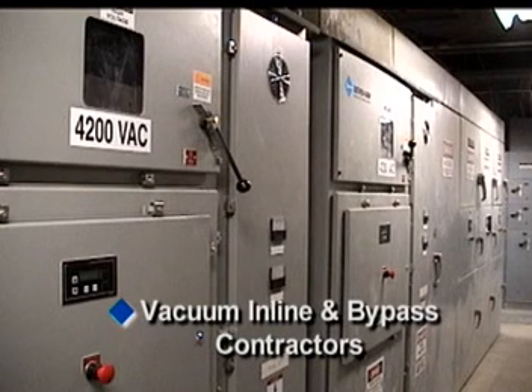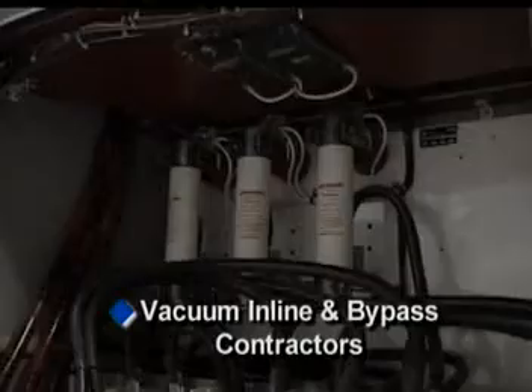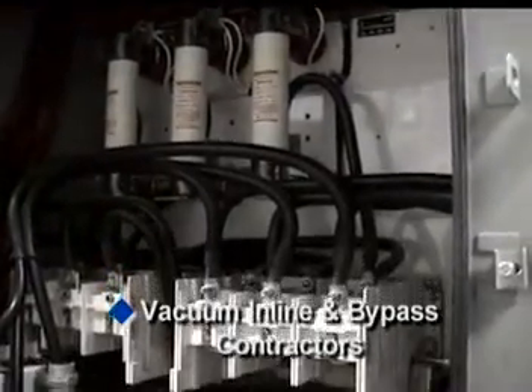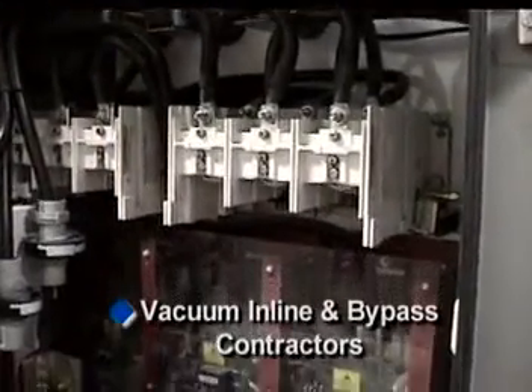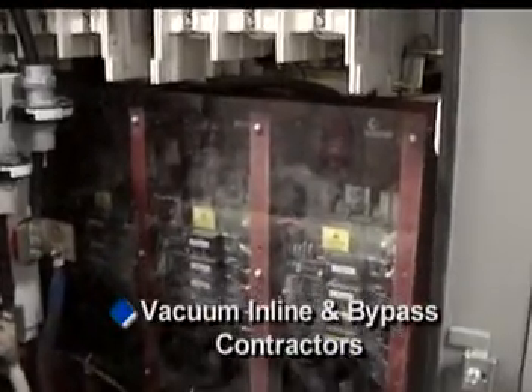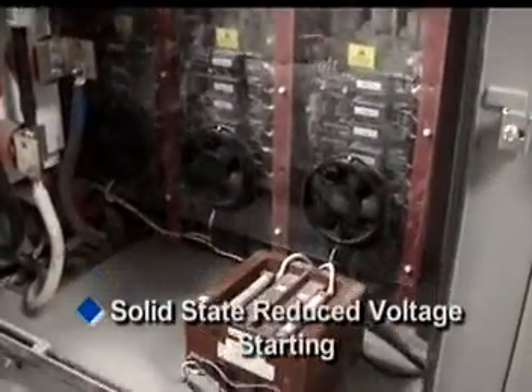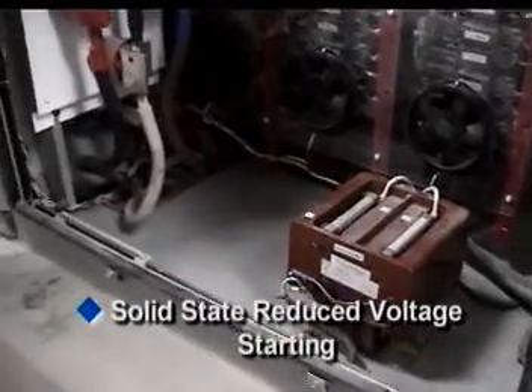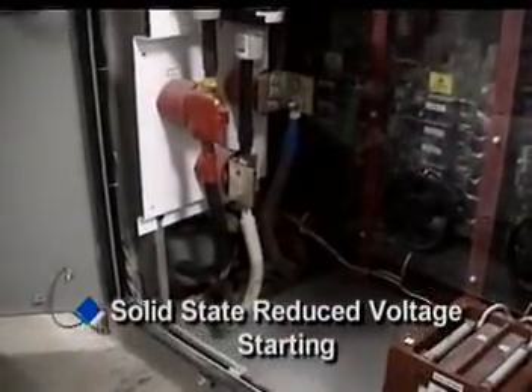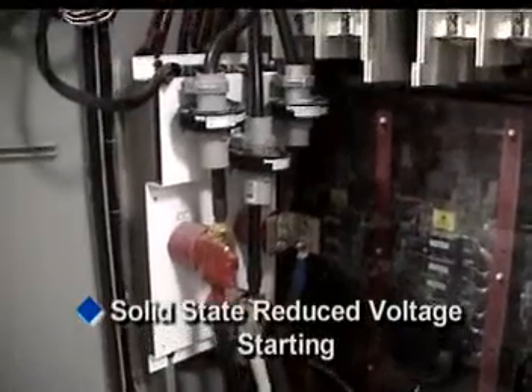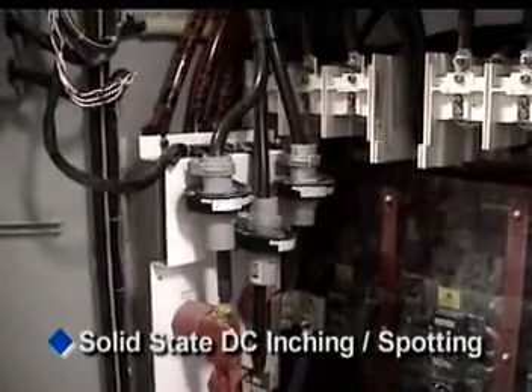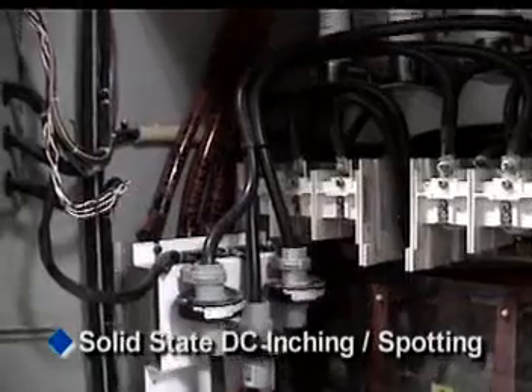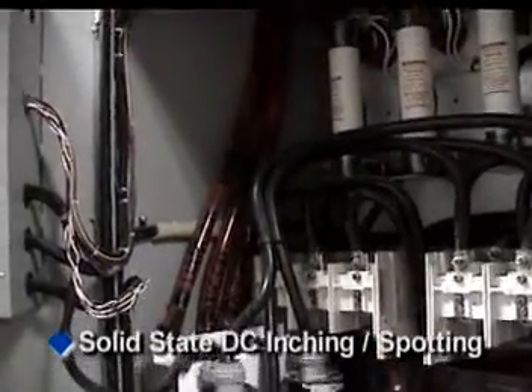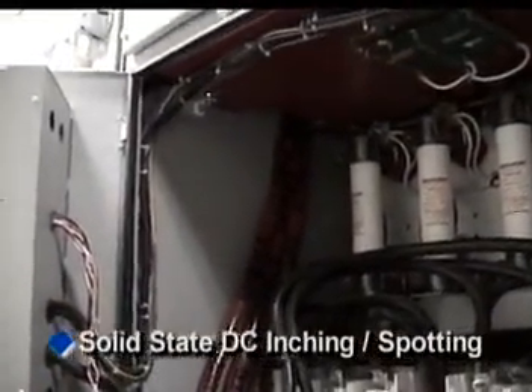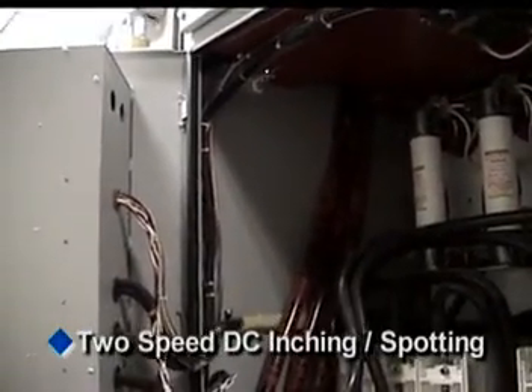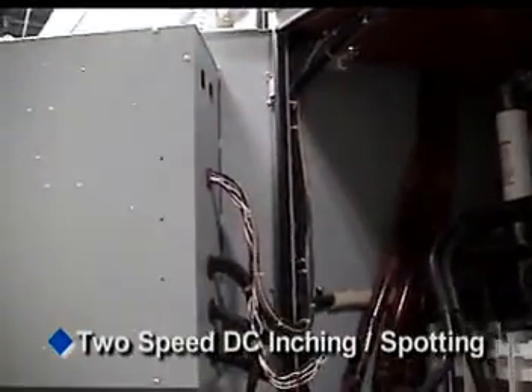Internally, each unit comes complete with 350 MVA short-circuit rated, fixed-mount, Class R fusing, vacuum line isolation, and vacuum SCR bypass contactors. A heavy-duty 3-phase SCR power section provides an adjustable, stepless soft start for reducing electrical inrush peaks and eliminating mechanical shock. During inch or spotting mode, the 3-phase SCR power section is fan-cooled and provides the rotating DC voltage and current to respective motor poles for magnetic interaction to the DC applied motor field.